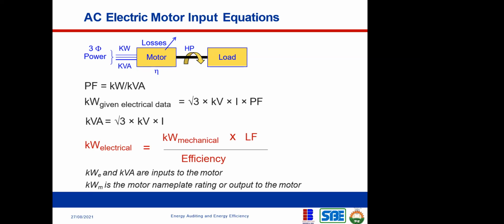The capacity written on the nameplate of your motor is the output energy, the power output of the shaft, which is kilowatt mechanical. In most cases, you will be asked to calculate the energy input, which is kilowatt electrical. You can know the kilowatt mechanical from the nameplate, but you now have to calculate what the energy consumption will be.